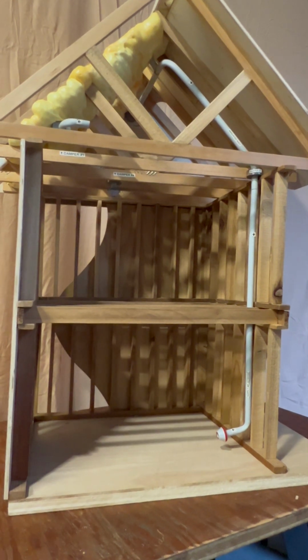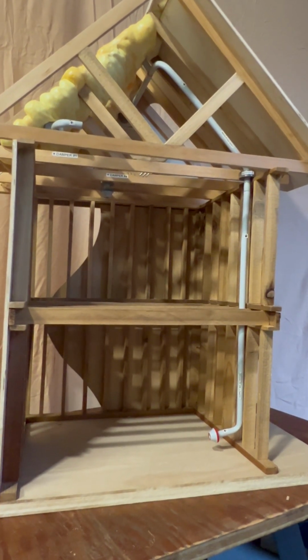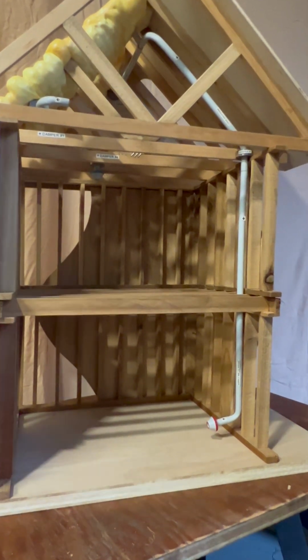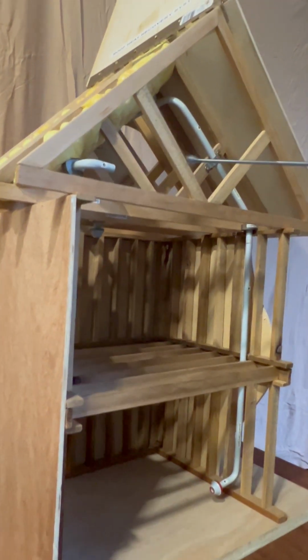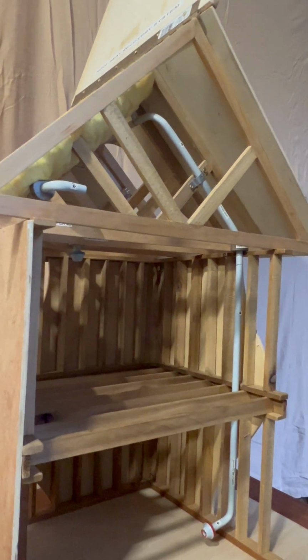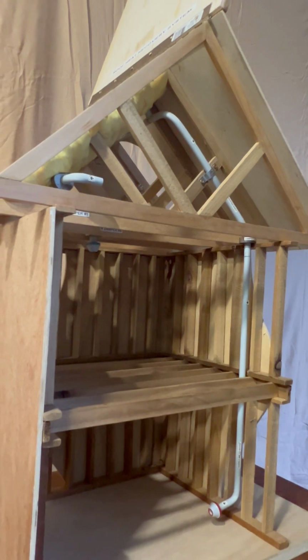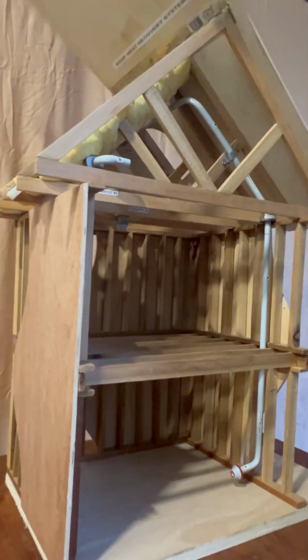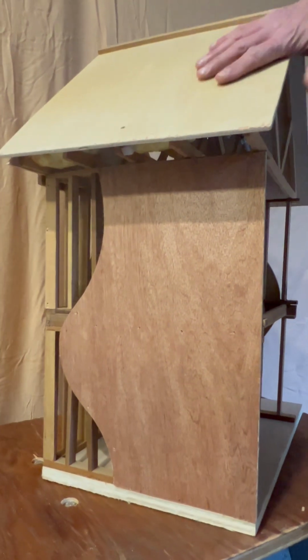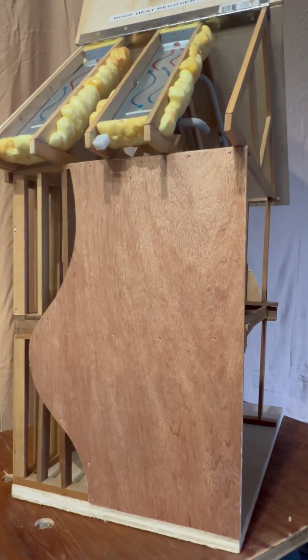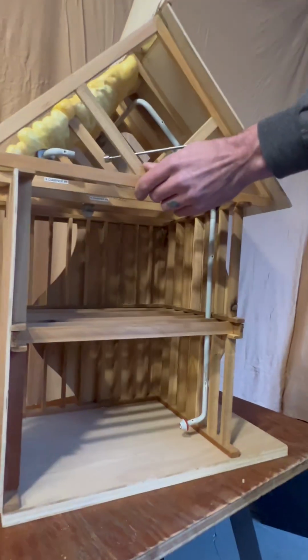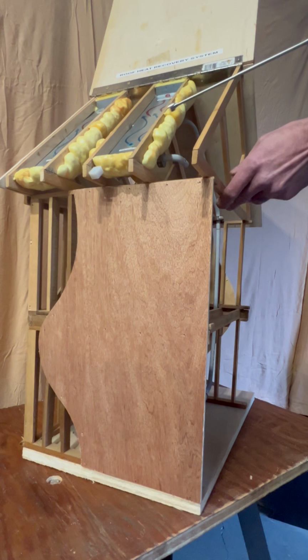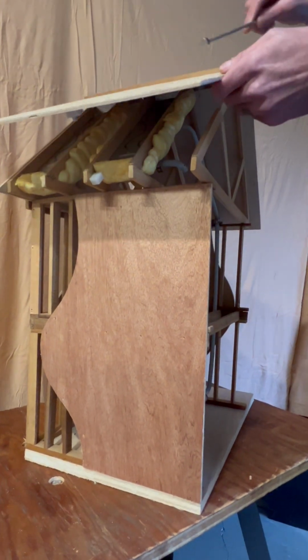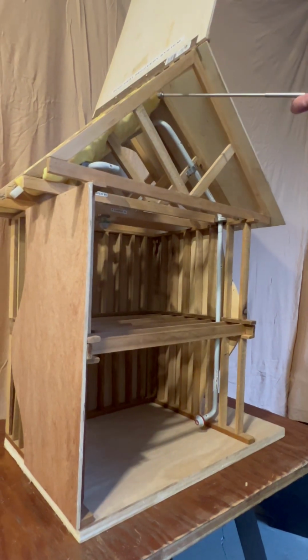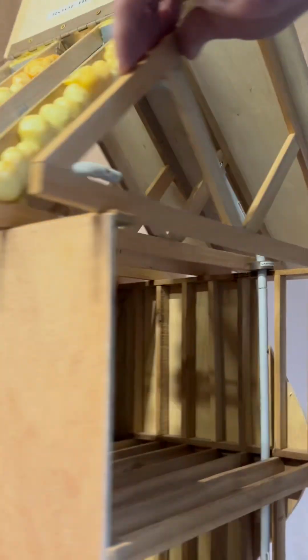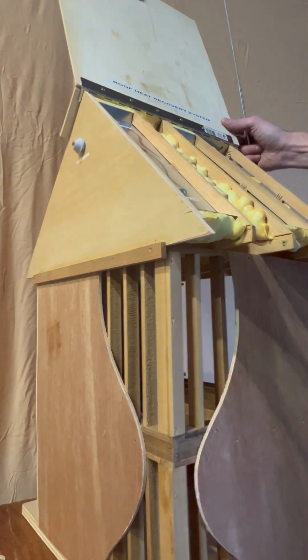The second mode of operation would be more in the summertime. So basically that's when the roof gets really hot and we don't really need the heat. And the general idea of an attic is to ventilate the attic and get rid of that heat, so we keep the dwelling at a nice temperature inside. So when the sun gets really hot, the roof surface gets really warm, the system kicks on automatically, and it actually draws heat from the attic, circulates that warm air through the panels. It gets even warmer as it cools the roof surface, and then that heat comes out the baffle, and then it actually is diverted and rejected to outside where it's unobjectionable.